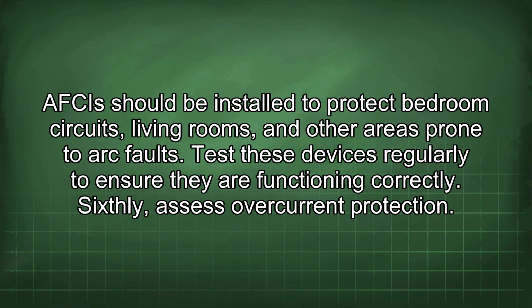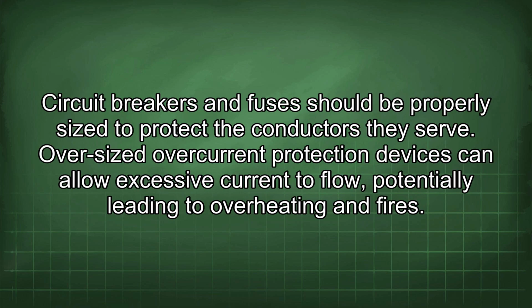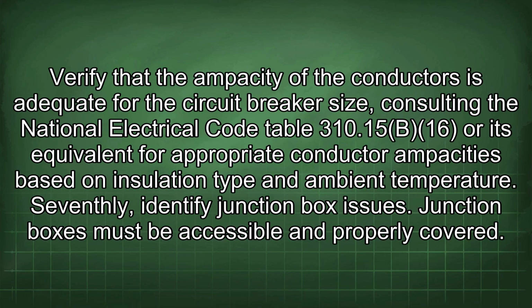Sixthly, assess overcurrent protection. Circuit breakers and fuses should be properly sized to protect the conductors they serve. Oversized overcurrent protection devices can allow excessive current to flow, potentially leading to overheating and fires. Verify that the ampacity of the conductors is adequate for the circuit breaker size, consulting the National Electrical Code Table 310.15(B)(16) or its equivalent for appropriate conductor ampacities based on insulation type and ambient temperature.